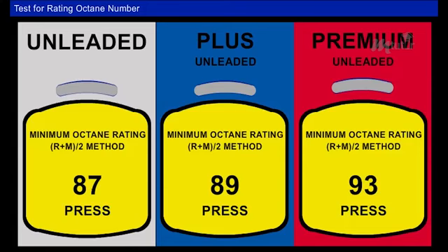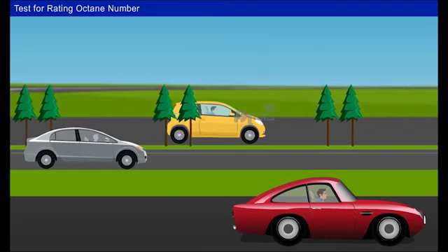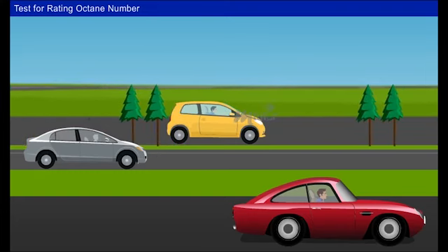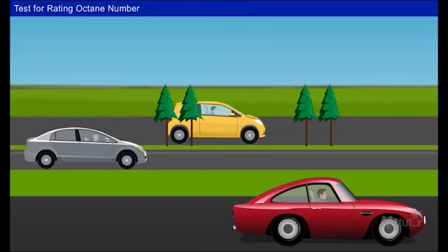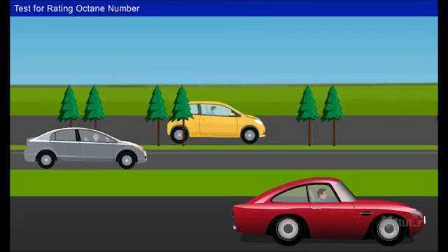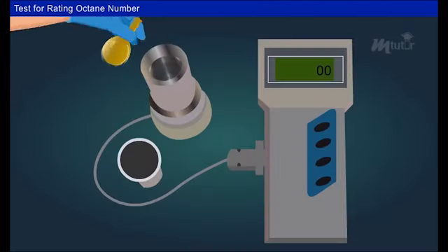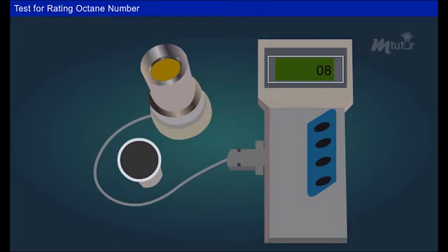Modern way to determine octane number. When fuels of different grades are produced, it is customary to have them tested for quality in typical test motor engines using that fuel. This method is time-consuming and expensive. So, it has been replaced by the more modern NIR spectroscopy. Based on a previous calibration, the octane number of the fuel is read out on the digital meter.